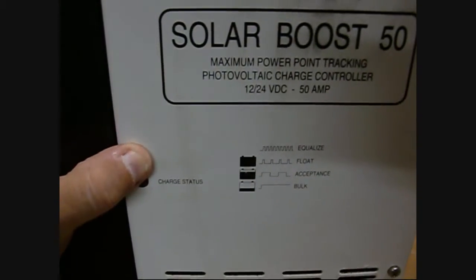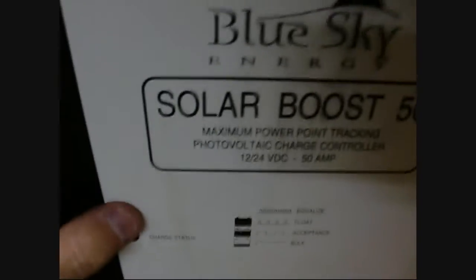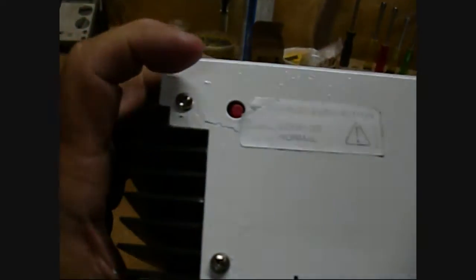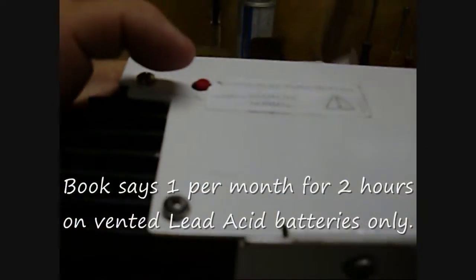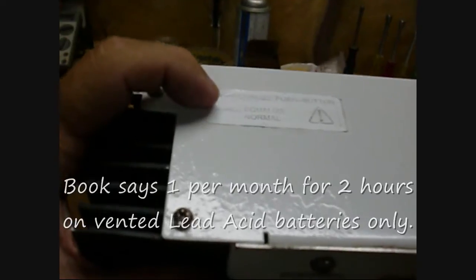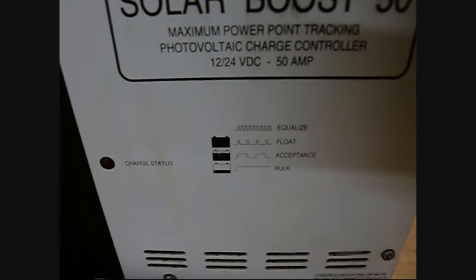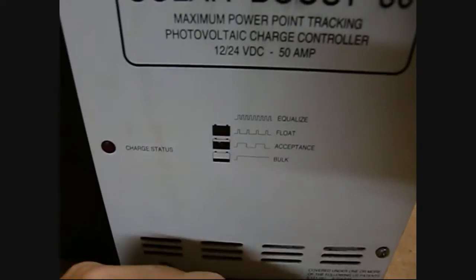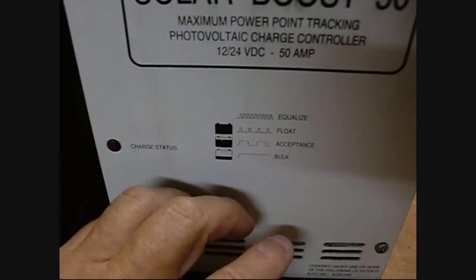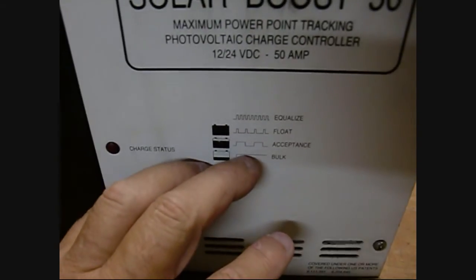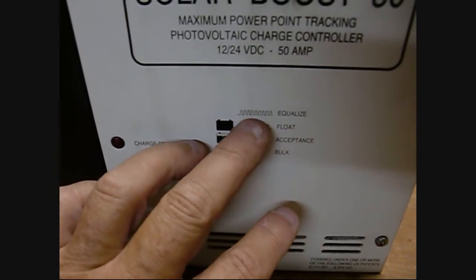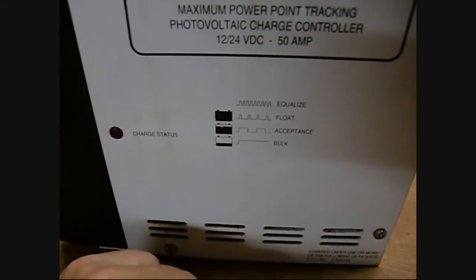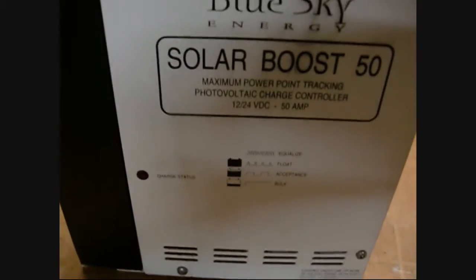It does have an equalize function that you do manually through a button up here. This allows you to manually run it in equalize mode. After many cycles of using your battery pack, some of the cells within the batteries will start to be a little bit out of sync with each other. By using this equalize function, it brings them all back to a standard level. Just read the manual to know how often to do that based on how you use it.